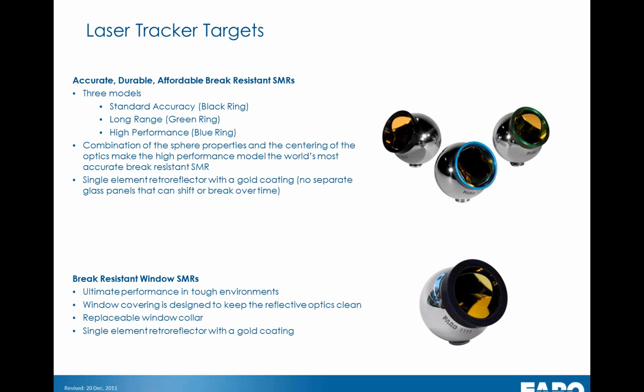And we also have break-resistant windowed SMRs as well. Now these allow us to measure in harsh and dirty environments, for instance, where there might be a lot of dust or a lot of moisture in the air, which could affect the optical surfaces of the SMRs. So we have a patented window that we can put across the front of them, which allows us to take measurements even in harsher conditions as well.